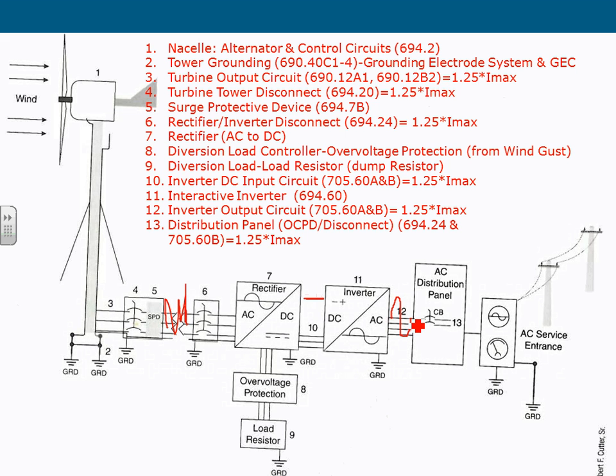You bring your conductor into number 11, the interactive inverter. Now you invert it back to AC. You need to bring a bunch of conductors here, typically 3 conductors for a 3-phase system, or 2 conductors for a 2-phase system. And you multiply it by 1.25, and you size your conductor as well as your overcurrent device, which acts also as your disconnect. So that number 13 acts as your overcurrent device, as well as your disconnect. So that's basically the block diagram and the sizing for the whole wind turbine.